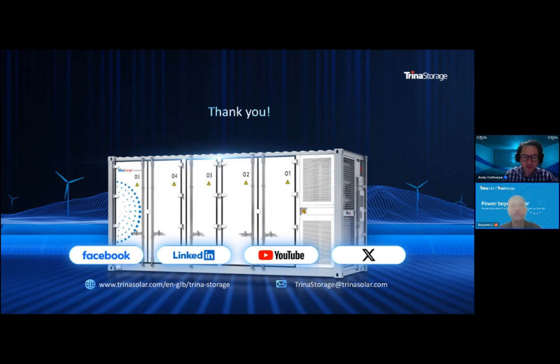Exactly. The life cycle test at the cell level is implemented in a way that considers 100% DoD at a 0.5P rate, or in some circumstances, we even test the 300 ampere-hour battery cells at a 1C rate.